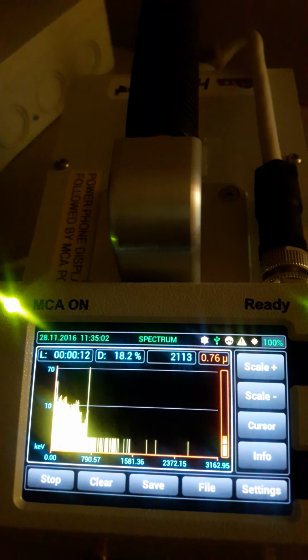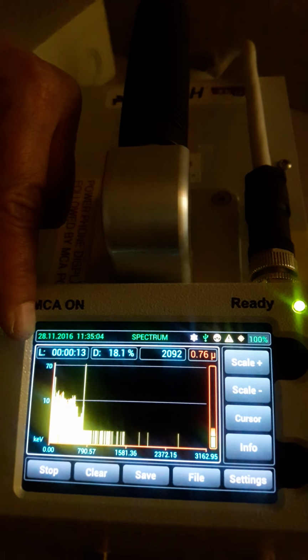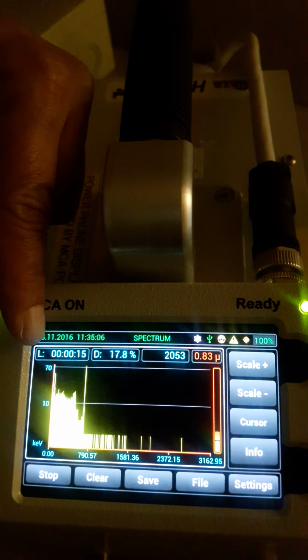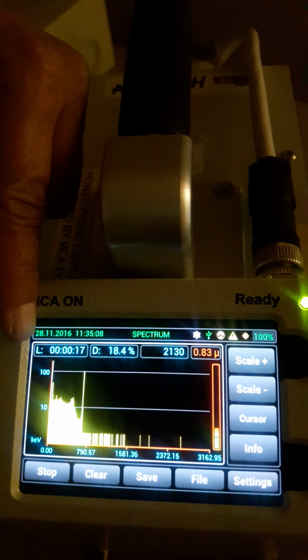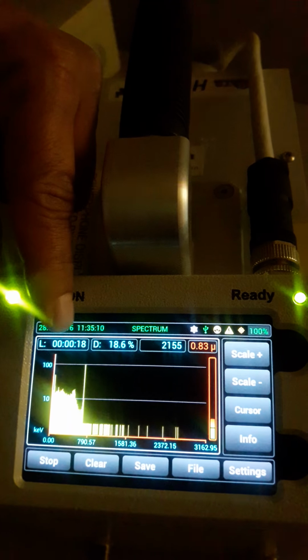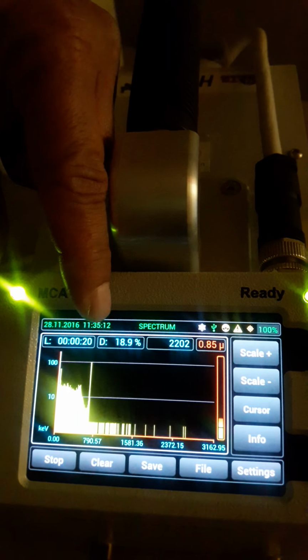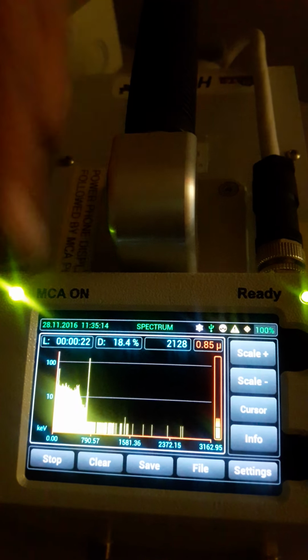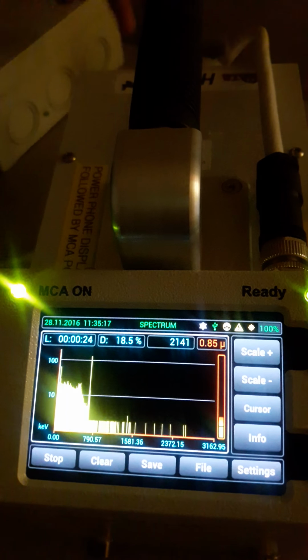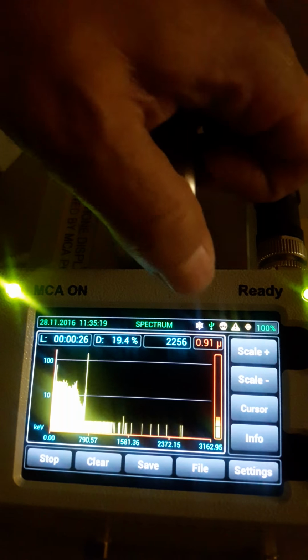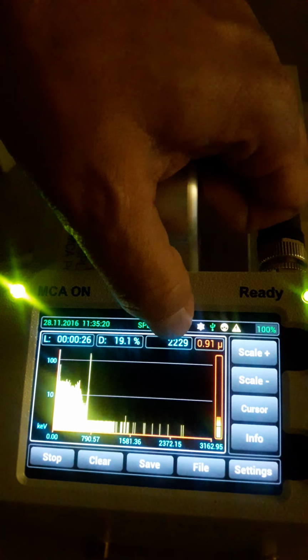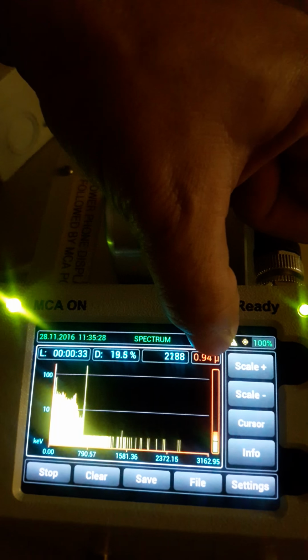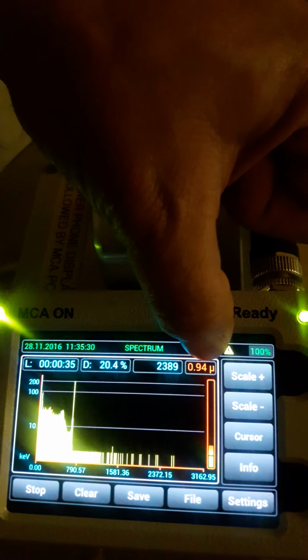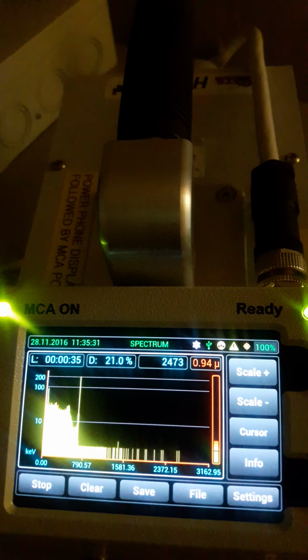So now let's look at the screen. On the left part in here, where my finger is, it's telling you what the live time is. It's telling me that 18 seconds have elapsed. The dead time of the system is 18%, because the source is fairly close to the detector. And then this gives you a total count rate, not the count rate on any peaks in here, but the total count rate that is detected from the source, and that's the dose information. So I'm reading 0.94 microsieverts per hour in dose.